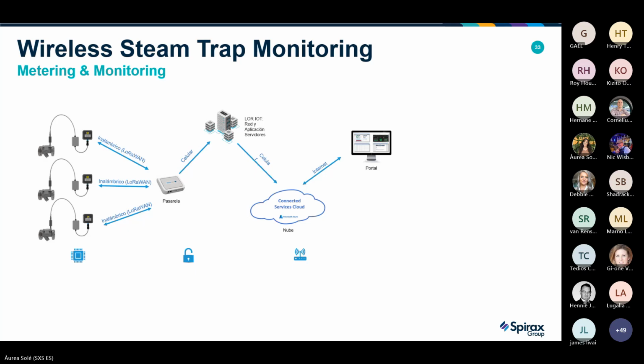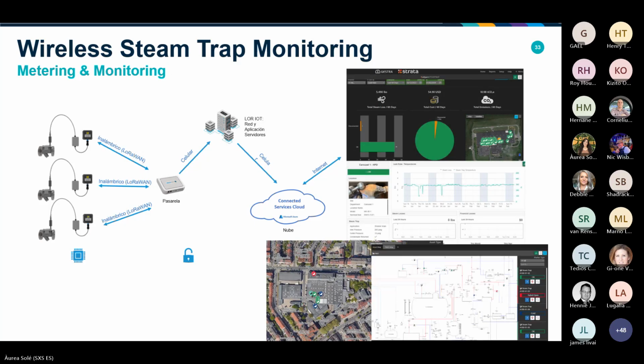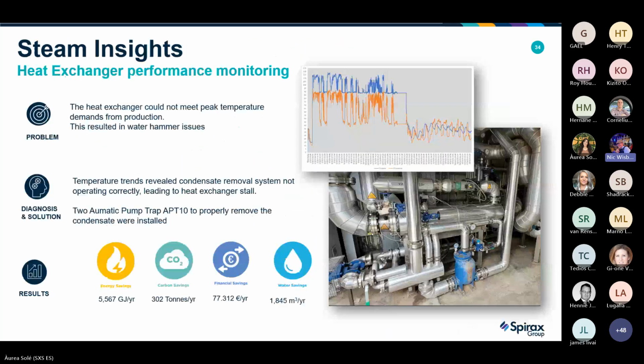Next slide, please. So, wireless steam trap monitoring. How it works is there's a sensor, as it shows on the trap on the left-hand side, and then it goes to your transmitter box. That's picked up by a router, which then transfers it to a computer system and then onto the cloud-based system. It's a little bit more difficult on that because the slide is in Spanish and I speak only English, badly, so I apologize for that. Next slide, please. So as this shows, okay, yeah.